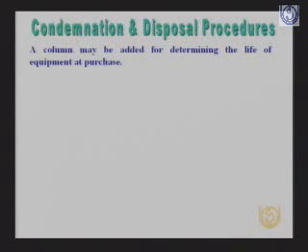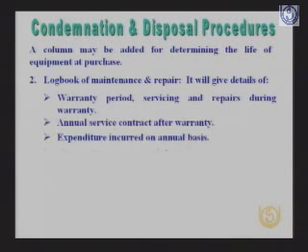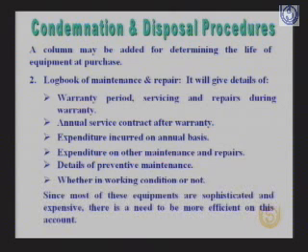Besides this, we can also maintain a logbook of the maintenance and repair, which gives you some of this information. The history sheet and logbook can be one integrated document in which all the details will come about how much expenditure is being incurred on its maintenance, etc.